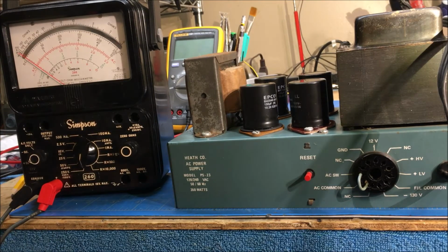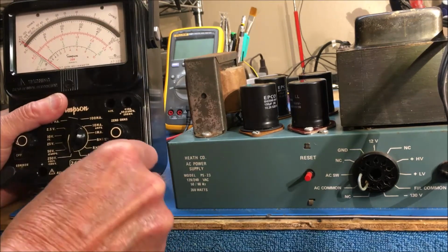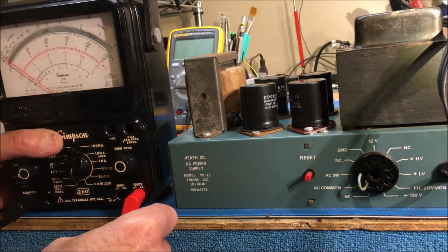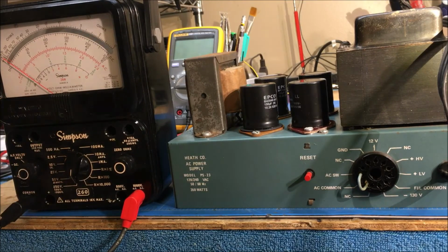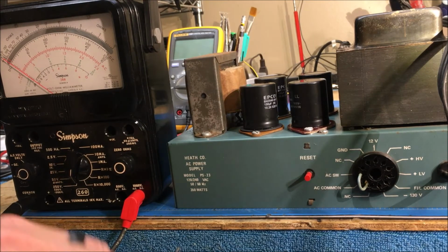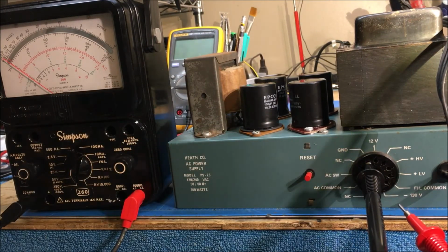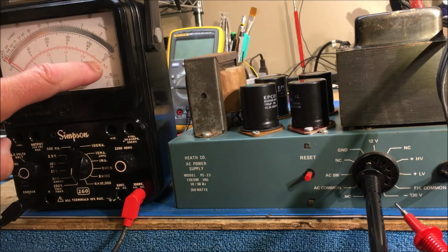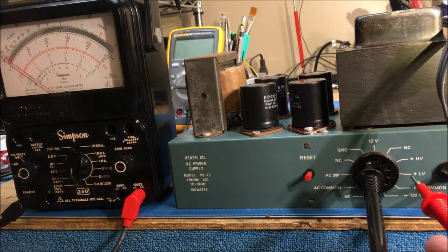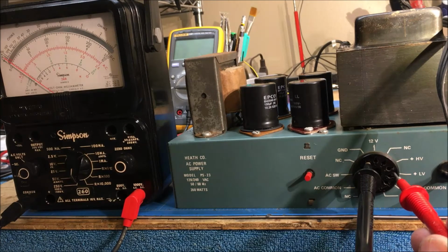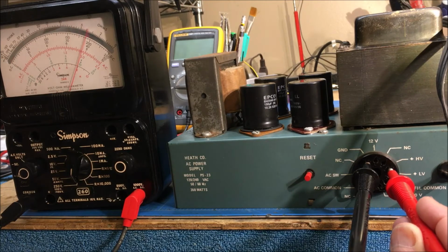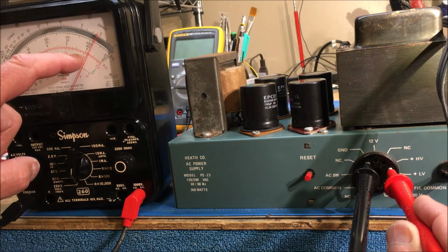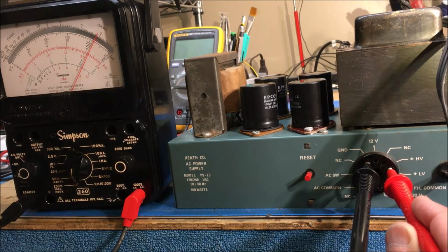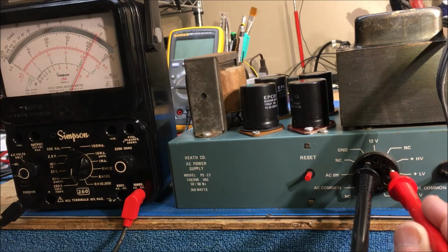Switch down to 1000. Now we've got to change to the 1000 volt plug or socket. We'll go to the ground, which is here, and we'll go to the high voltage, and we're on the 1000, which is this where it shows 10 just above the red there. So let's go to the high voltage, and we're reading 800, 10, 20, 820. The specs call for 820 unloaded, and that's what we've got.